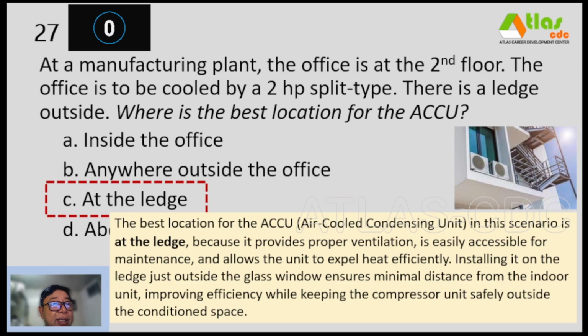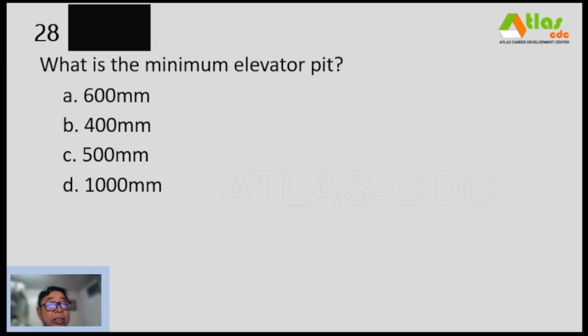And our correct answer is C, at the ledge. So the best location for the ACCU or air-cooled condensing unit in this scenario is at the ledge because it provides proper ventilation, is easily accessible for maintenance, and allows the unit to expel heat efficiently. Installing it on the ledge just outside the glass window ensures minimal distance from the indoor unit, improving efficiency while keeping the compressor unit safely outside the conditioned space.